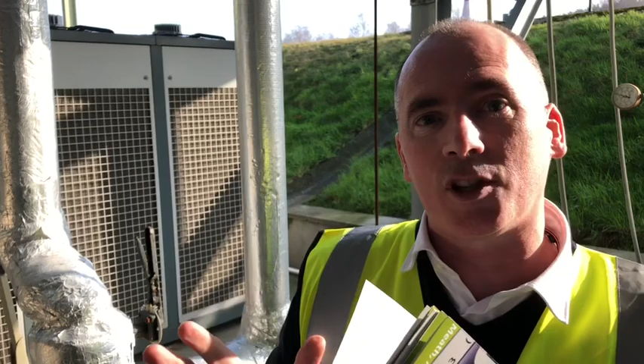And the reason being simply size. With a chiller that has an integral free cooling coil, we're limited very much by the size of the coil, and consequently the ambient typically has to be a lot lower to get much more free cooling. Whereas with this system we can select with our software whatever size we want, so we can give 100% free cooling at a much higher ambient temperature. So basically, if you have space available, we can give a lot more free cooling.